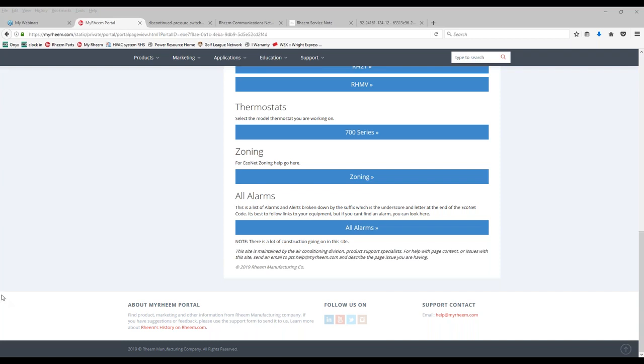All right, one thing we're looking at with the humidity, we did have a question on that. It looks like if you select to test the humidifier, it says change the humidify set point up to test. So apparently the set point will go all the way up to test is what they're saying. Select humidify during heat and fan. When you humidify during heat/fan, then turn on a continuous fan speed on the settings screens of the Econet thermostat. This should force the humidifier to run.